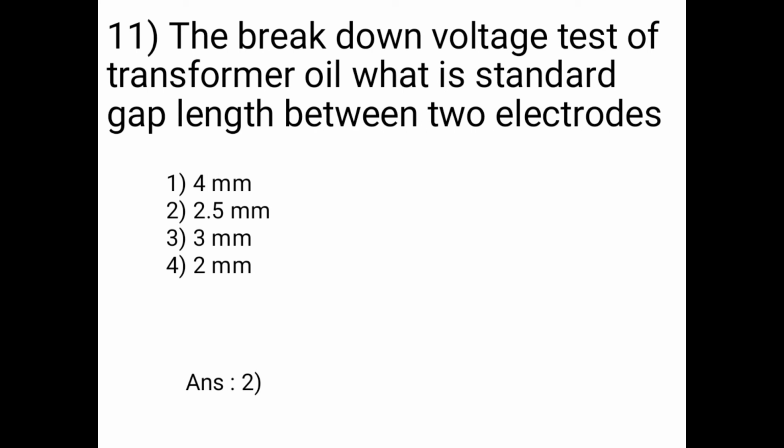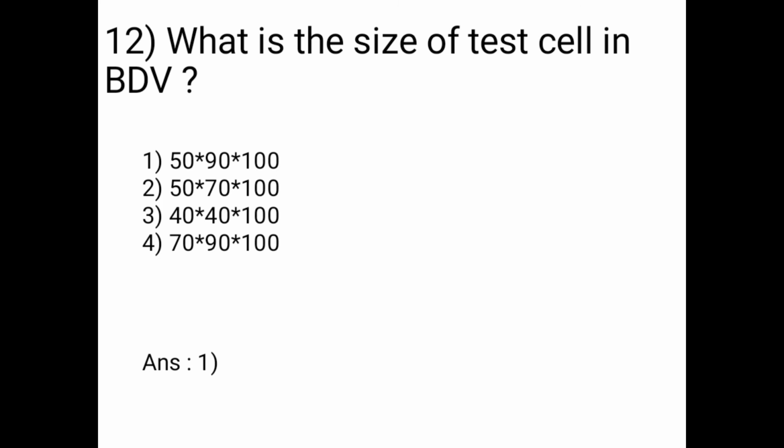In the breakdown voltage test of transformer oil, the standard gap length between two electrodes is 2.5 mm. Question number 12: what is the size of the test cell in BDV? So the correct answer is option 1, 50 into 90 into 100.